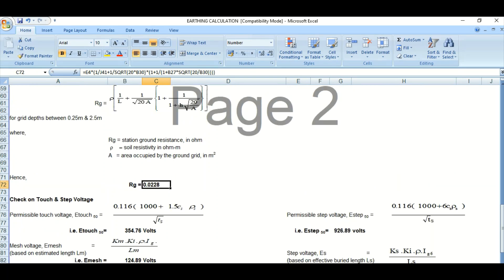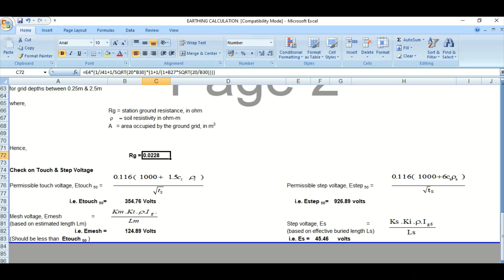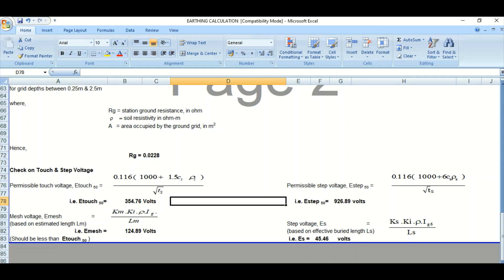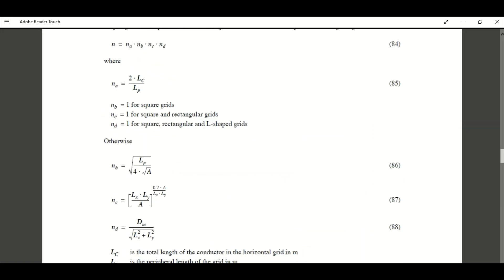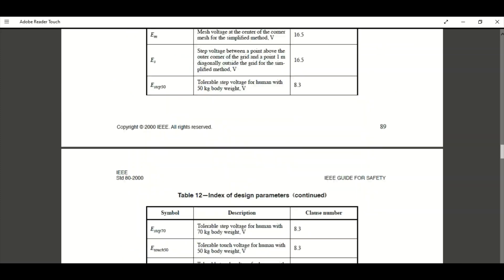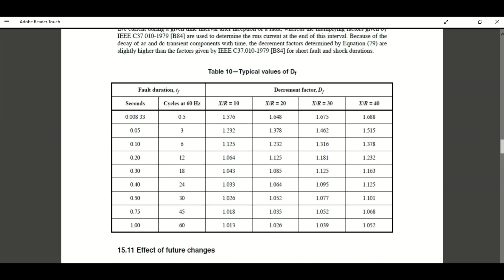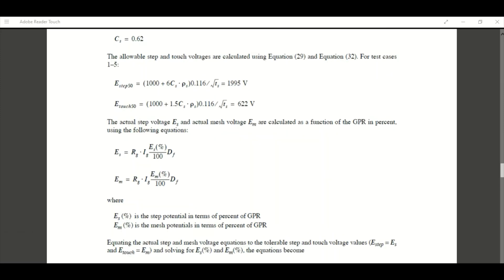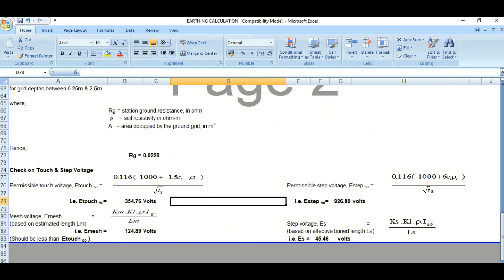To calculate the permissible touch voltage, Etouch50 for a 50 kg body weight — this is the formula from IEEE 80. Similarly, the permissible step voltage Estep50 formula is also from IEEE 80. Using these formulas, the Etouch50 value comes to 354.76 volts — this is the permissible touch voltage.